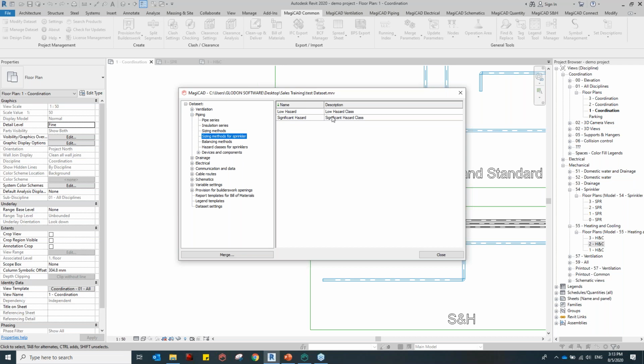Sprinklers are a bit different here. You have a low hazard class, so you can create your own sprinkler tables. You just need to specify 3 sprinkler 25, 4 sprinkler 32, 5 sprinkler 40, or 10 sprinkler 50 - these are the ones we commonly use.